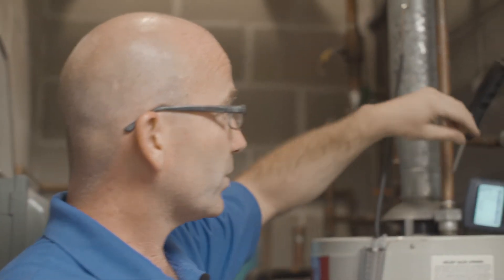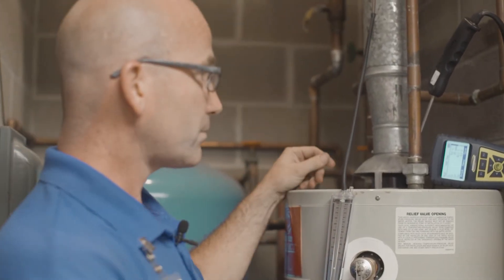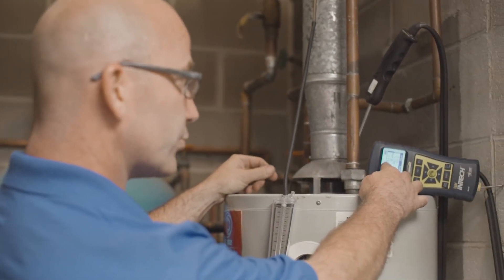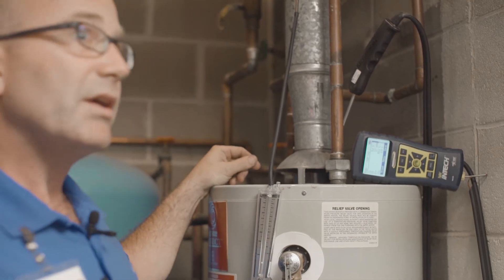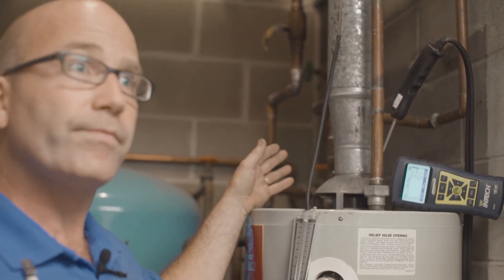They can be dangerous, meaning the reason we use the combustion analyzer at the same time as the draft gauge. Carbon monoxide right here is at 26 parts per million. If that were sitting at 400 and this was also not drafting properly, that 400 parts per million would be spilling out of this draft diverter into the home and that could have a very serious effect on the homeowner, meaning in a negative way.